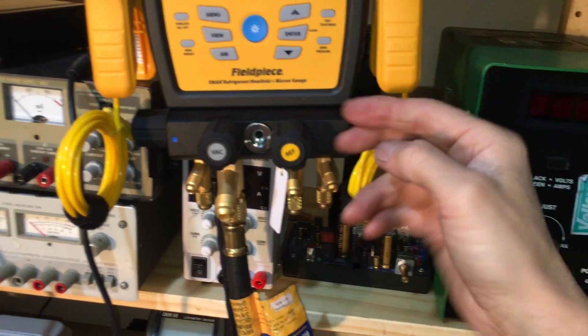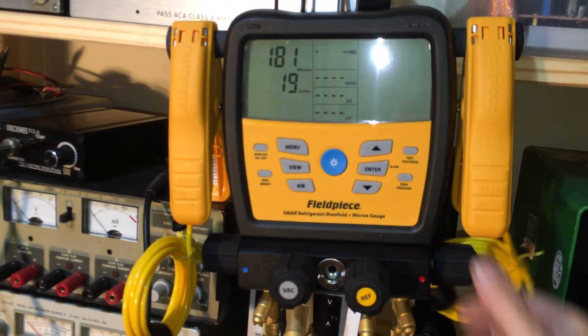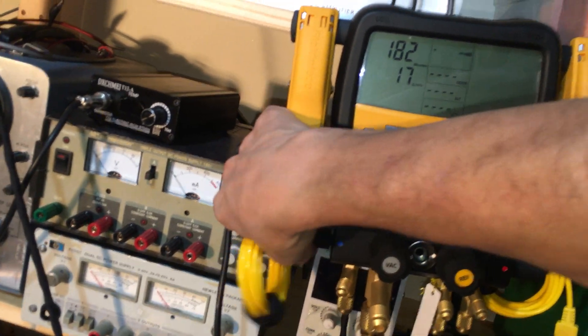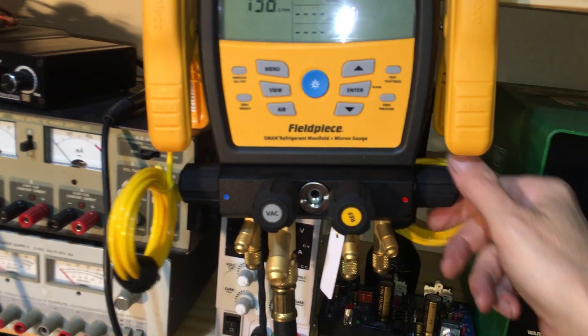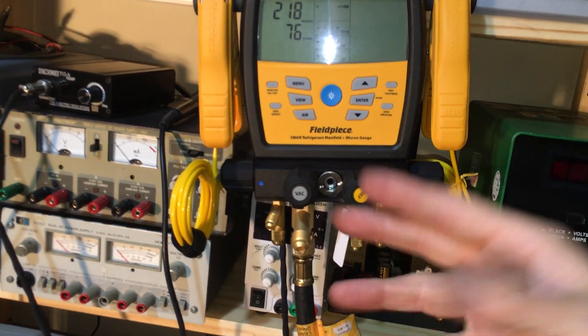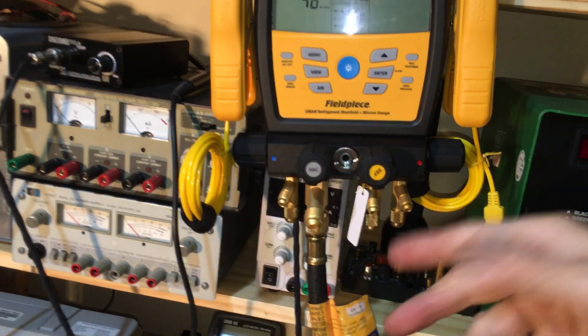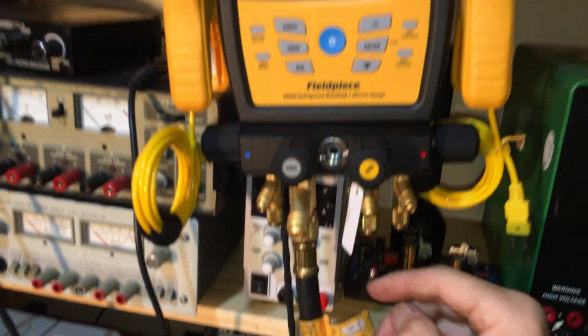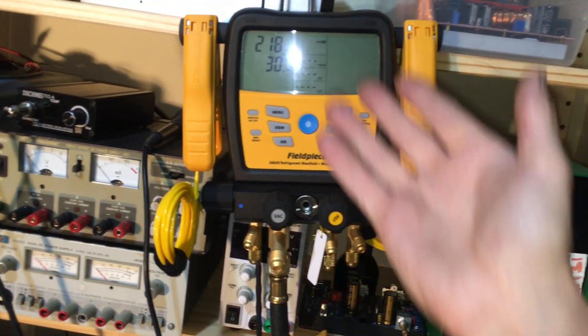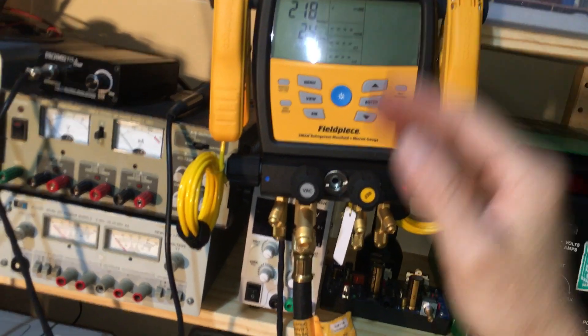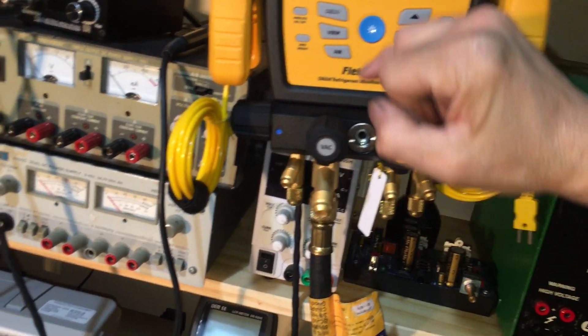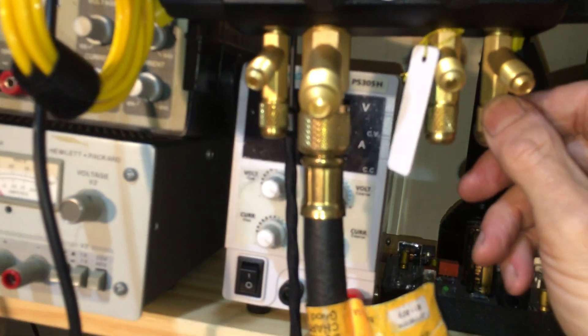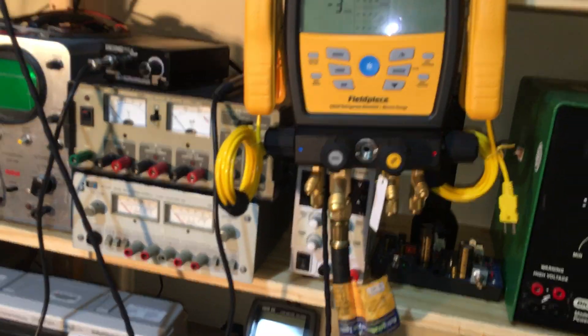Now you see that little jump right there? I first performed this with the valves all the way open, or almost all the way open, and proceeded with this test. It passed. Then I performed this test with the valves closed because I wanted to see if there's anything. This would be considered somewhat of a pass. It didn't go above 500 or so. I'm pretty convinced that I am good through the valves and also good through where the brass meets the body.